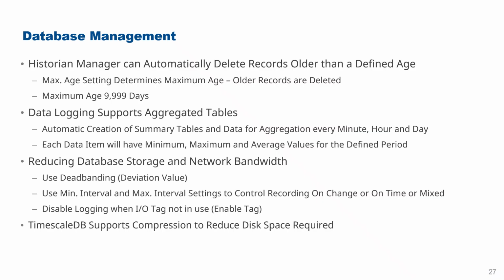So rather than store all of those data changes where you're just measuring the ripple on top of the surface inside your vessel or tank, maybe you set a dead band of 2 or even 5, and then you would only record changes when they exceed that deviation value. That way you're not recording those small ripples, you're only recording the actual bigger changes, and that can significantly reduce the amount of database storage you need. And of course, if you're sending data over a network, it reduces the amount of network bandwidth as well.